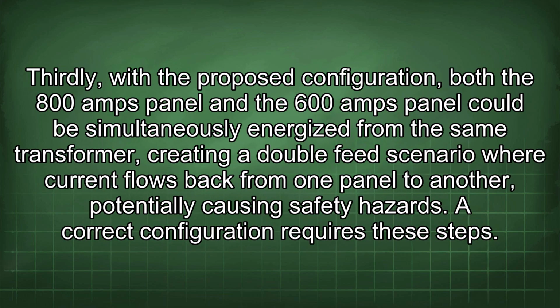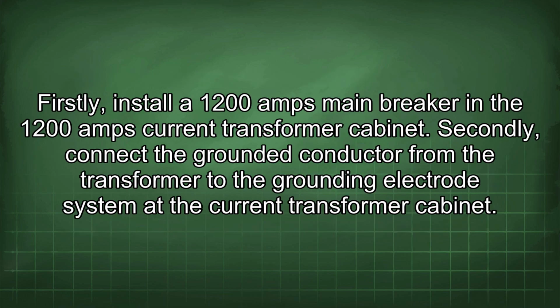Thirdly, with the proposed configuration, both the 800 amps panel and the 600 amps panel could be simultaneously energized from the same transformer, creating a double feed scenario where current flows back from one panel to another, potentially causing safety hazards. A correct configuration requires these steps. Firstly, install a 1200 amps main breaker in the 1200 amps current transformer cabinet.